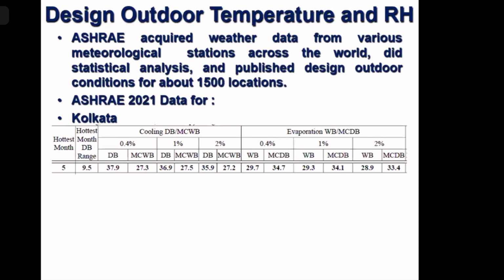But for very specific cases, if the outdoor temperature goes up, what will happen? My room temperature will go up, because my AC plant is undersized for that temperature. So it will not be able to cool properly. And for a very specific case where even for a very short time we can't tolerate that slightly higher temperature, then we should go for 0.4%. Otherwise, for general application, it is 1%. For offices, hotels, hospitals, residences, schools, everywhere we normally consider 1% occurrence level.